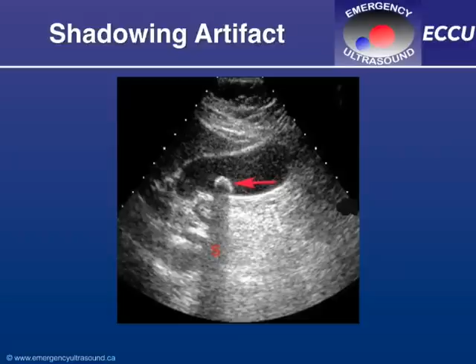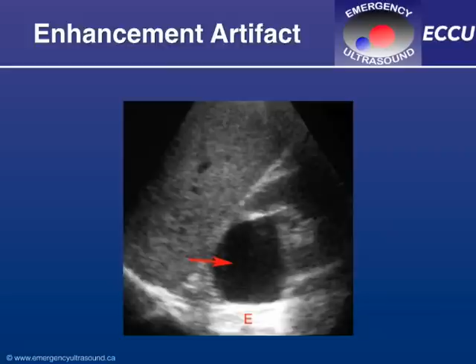A shadowing artifact is very simple. When sound waves are reflected, anything beyond that point in the far field, or deep on the screen, will in fact be a shadow, as demonstrated here with the gallstone. Enhancement is the opposite effect. As sound waves are not attenuated or reflected by fluid-filled structures, such as cysts or the bladder, more energy is transmitted beyond it, therefore there is more reflection far to the fluid-filled object. This leads to a brighter picture. This is called acoustic enhancement. Again, the gain or volume can be reduced to minimize the glare from such a bright reflection.